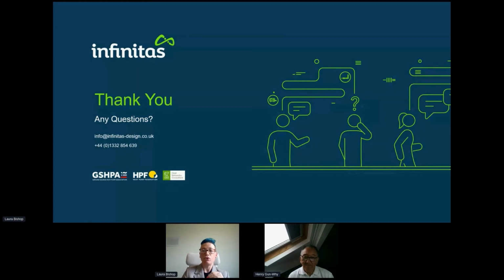Yeah, so before you get anywhere near placing orders for heat pumps, you will have already talked to the DNO, and they will have already confirmed that you've got sufficient capacity, no problem, or that you need to upgrade 100 kVA or you need a new transformer or something like that. That will then have been factored into your cost model, and if the project still works financially, then you can go ahead and get that done.